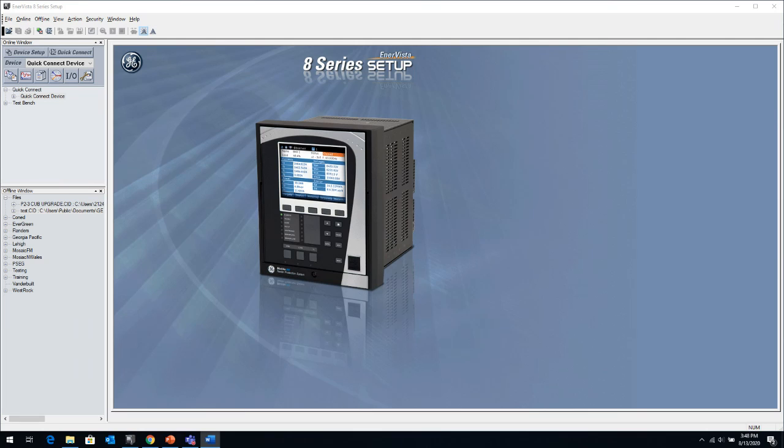This was back when you were talking about the impedance grounded systems and the Petersen coil. Somebody asked a question about Con Ed, in reference to that slide: is this why Con Ed likes to do ping testing? I figure they're not talking about pinging the network, so I was hoping with your experience you might have a better take on what this person might be asking. So Con Ed does not use Petersen grounds that are high impedance.